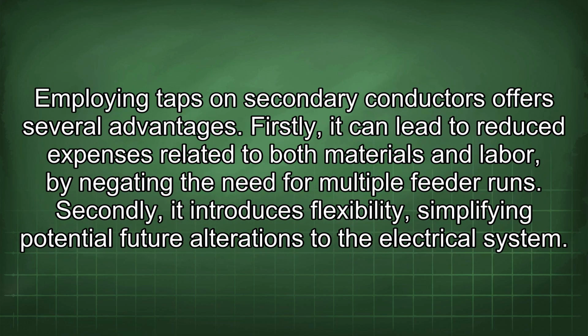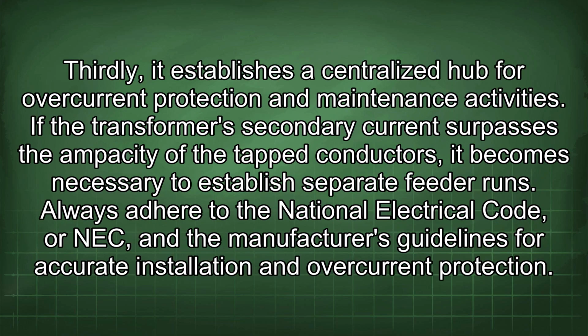Employing taps on secondary conductors offers several advantages. Firstly, it can lead to reduced expenses related to both materials and labor by negating the need for multiple feeder runs. Secondly, it introduces flexibility, simplifying potential future alterations to the electrical system. Thirdly, it establishes a centralized hub for overcurrent protection and maintenance activities. If the transformer's secondary current surpasses the ampacity of the tapped conductors, it becomes necessary to establish separate feeder runs. Always adhere to the National Electrical Code, or NEC, and the manufacturer's guidelines for accurate installation and overcurrent protection.